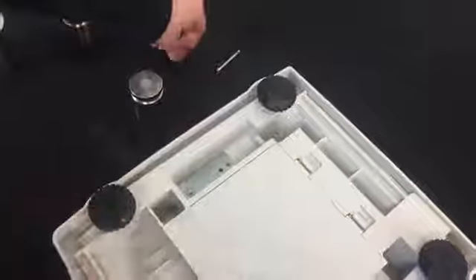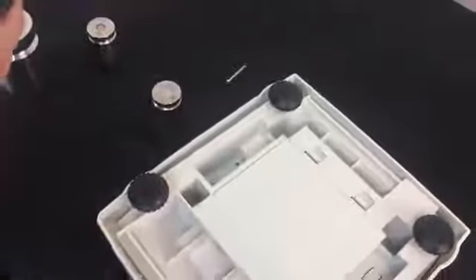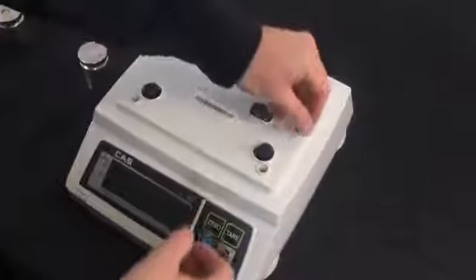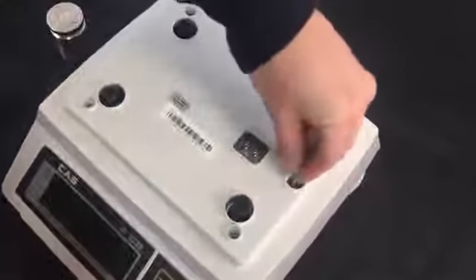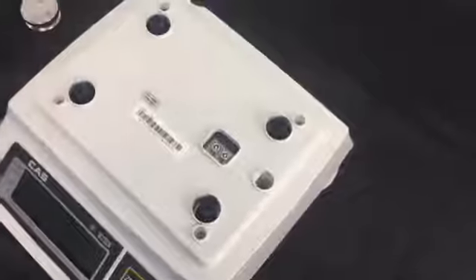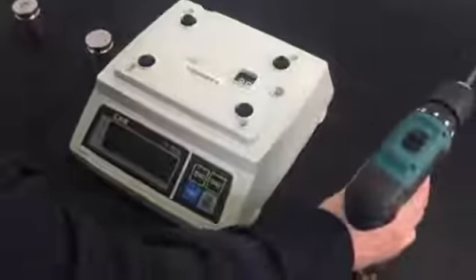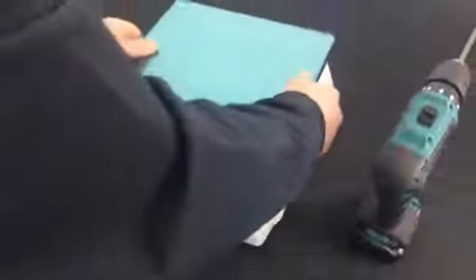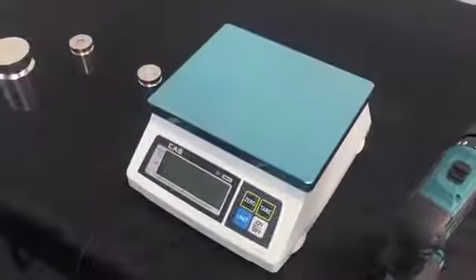Flip this around again. Place that calibration switch back in. Once we have the calibration switch back in, make sure we get the screws back in the right place. Flip that around. Long screw down in the hole. And that's it. We're all set. Fully calibrated.